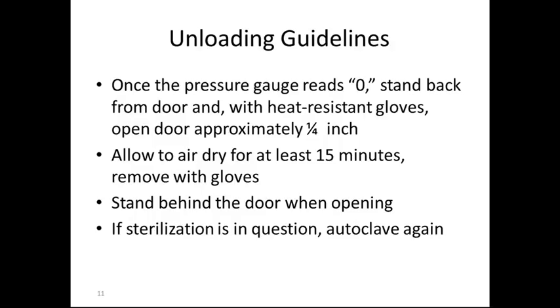Stand behind the door when opening. If sterilization is in question, autoclave again. It is important to let the materials dry and allow that 15 minutes after the door is opened, because if materials are handled and they are not dry, they are considered no longer sterile.